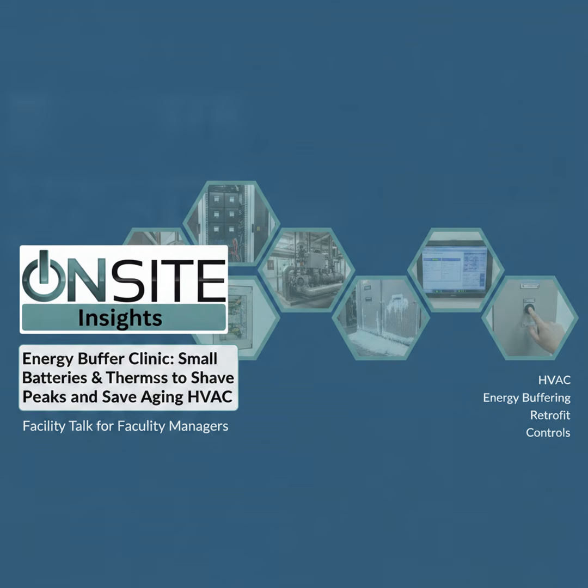Short field win. Community college rooftop. Baseline showed frequent short cycles. We installed a 24-volt UPS on the control bus, added a battery-backed relay on the contactor coil, tuned the BMS to suppress 1-second faults, and logged for 48 hours. Result? 2 avoided service calls and no compressor welds. The facilities lead called it a tiny, glorious victory.